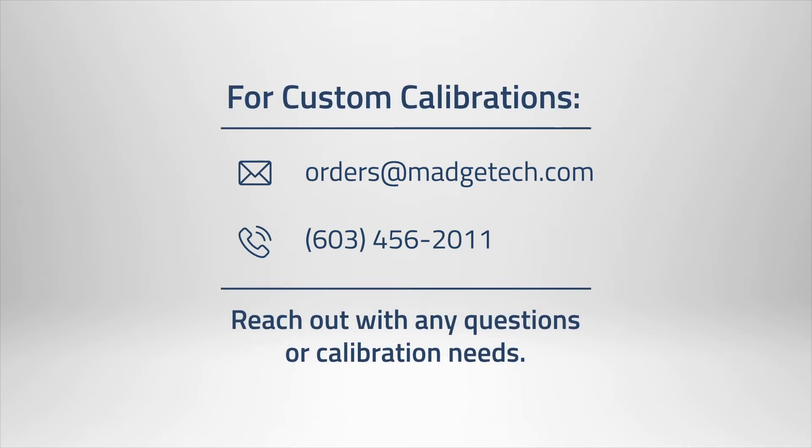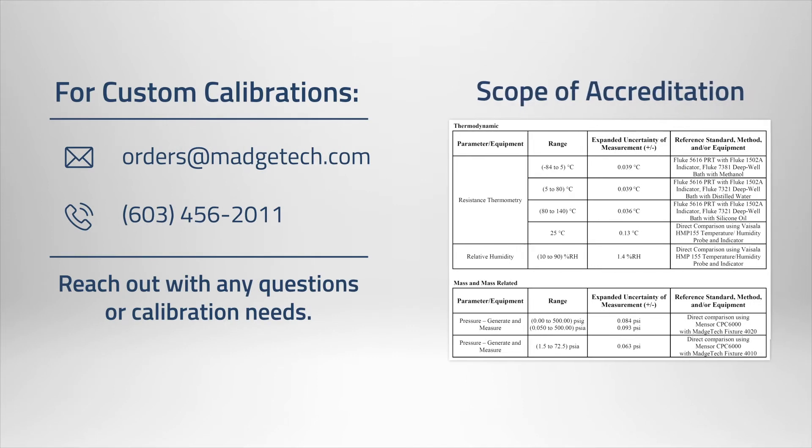We offer both standard and accredited calibrations for our MadgeTech devices, and if preferred, customers may also send in their loggers with their own specified custom calibration requirements, which may also receive an accredited certification so long as the points fall within our scope.